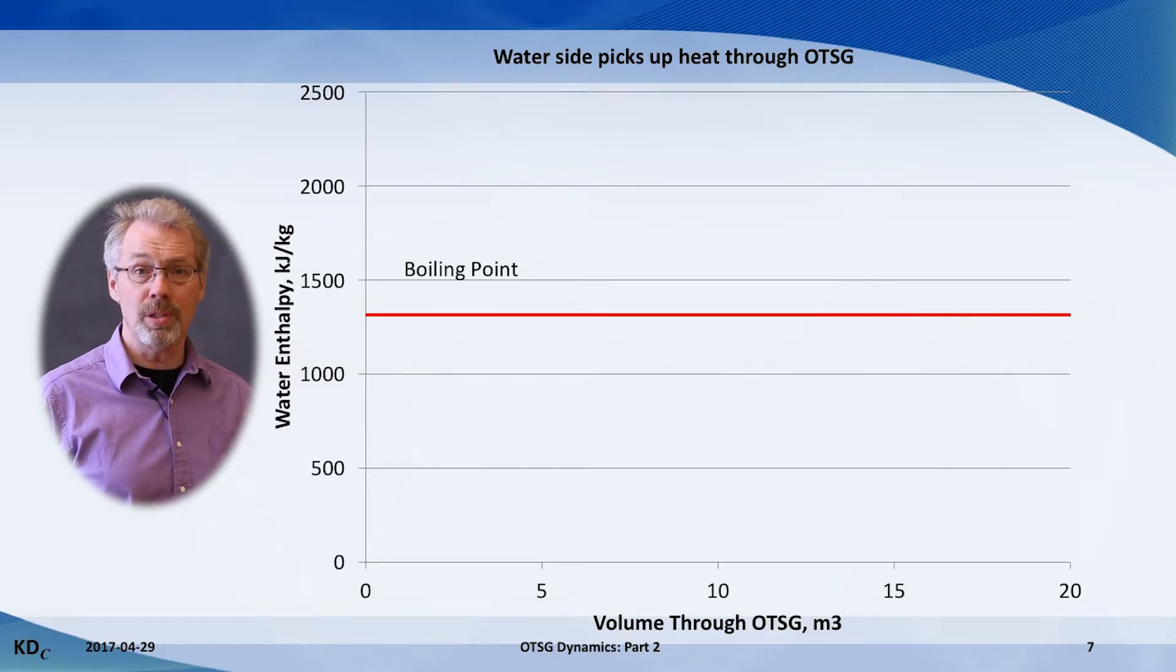On the vertical axis is the enthalpy, or the heat content of the material. The fluid enters the OTSG at 600 kilojoules per kilo, or about 150 degrees Celsius. As the fluid creeps through the convection section, it picks up heat from the hot flue gas, and the water gets warmer.